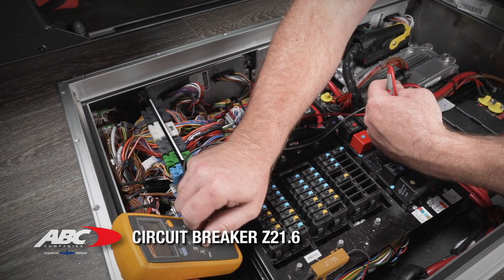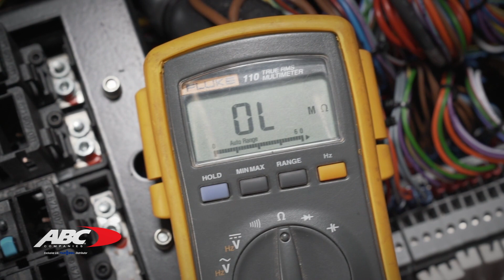Our readings show no significant change. Next, we have circuit breaker Z21.6. Remove the circuit breaker and check both sides of the contacts. We have two different readings, which means there is an open circuit. Replace the breaker and recheck at node 4.